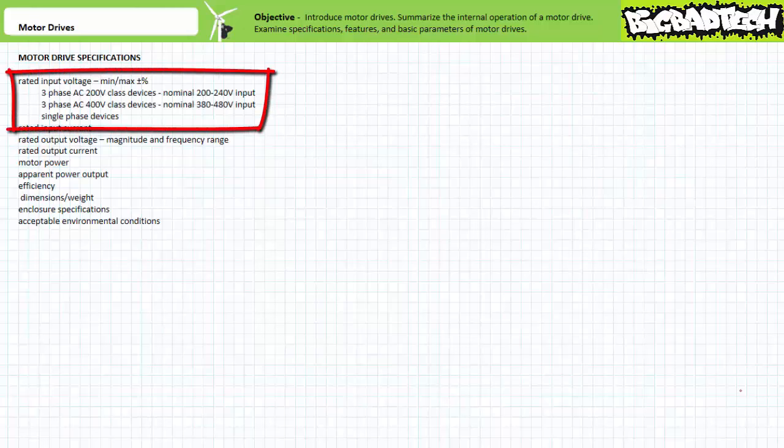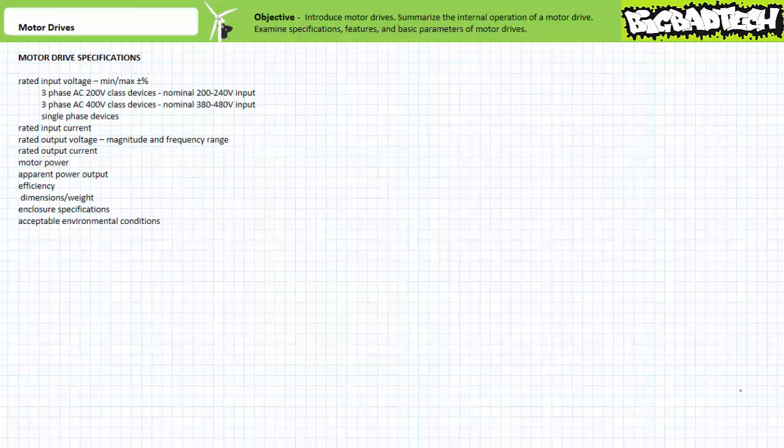Most motor drive manufacturers divide their offerings into three general product classes: three-phase 200-volt class devices including three-phase AC distribution systems with nominal 200 to 240 volt values; three-phase 400-volt class devices including three-phase AC distribution systems with nominal 380 to 480 volt values; and single-phase devices. These are arbitrary distinctions — certain manufacturers may divide into more or fewer classes and offer motor drives operating at higher voltages. There also exist motor drives that make use of single-phase AC input.